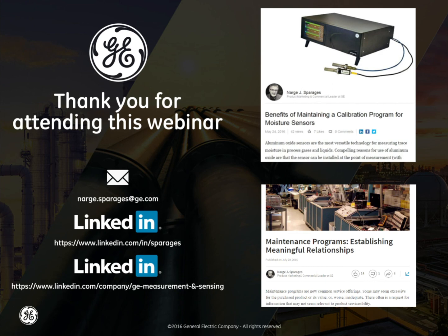Just to give everyone context, in cold regimes, the moisture content expected is around 2 pounds of water per million standard cubic feet of natural gas. As you get into warmer climes, it's 4 and 7. And at 7 pounds of water, you're at or around 100 ppm. The sensor is expected to change in calibration by around 2 degrees C dew point between 6 and 12 months.